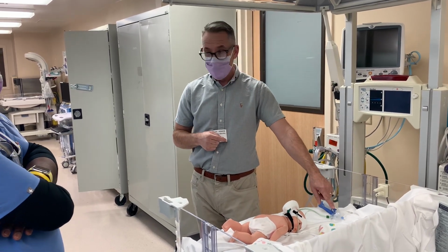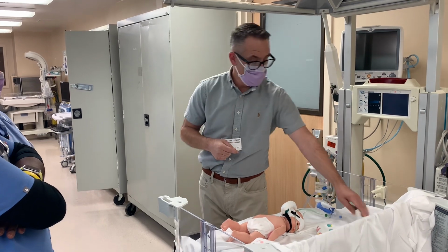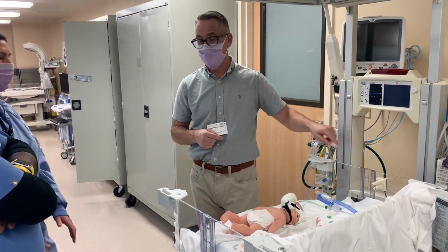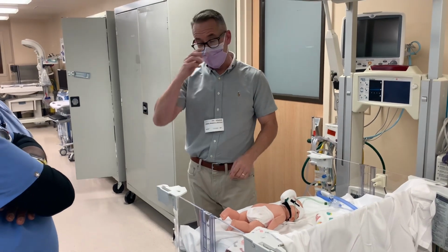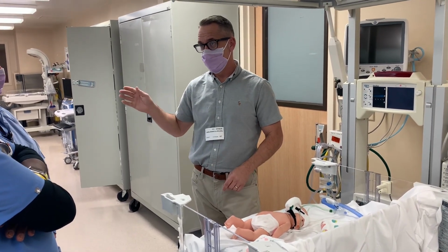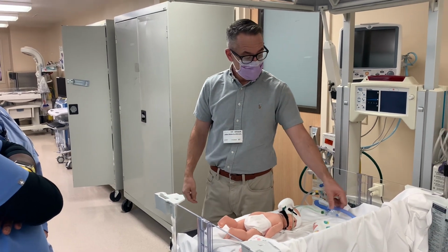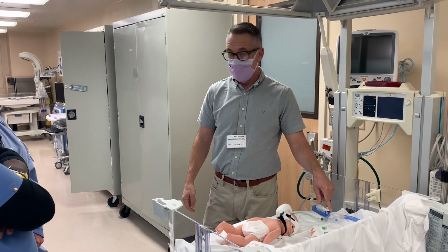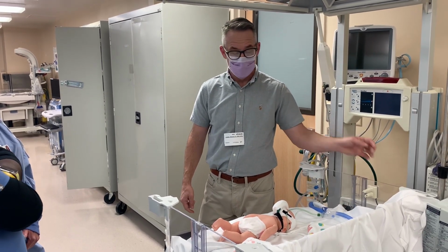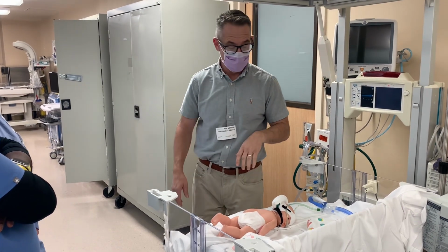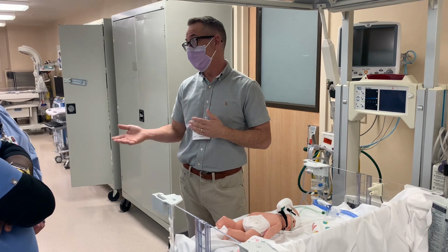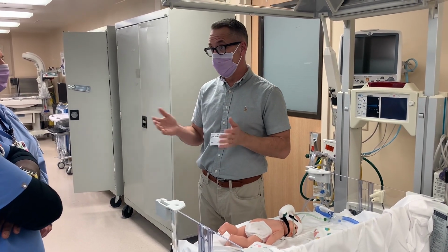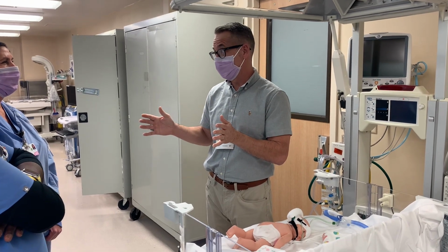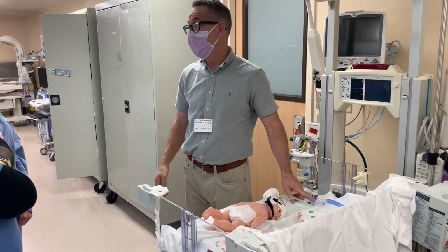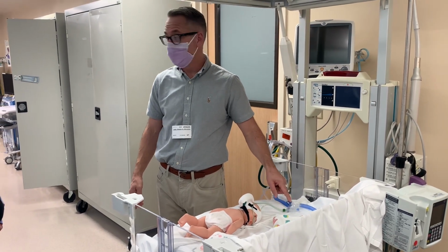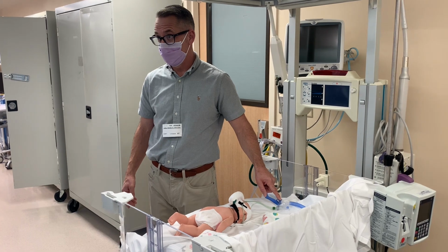People ask, why are you allowing the temperature probe now in the incubator? I've always been told I need the extension unit because we want the temperature probe outside the incubator. The reason why is that back when we used old incubators, we used to set the temperature to 36, 37 degrees manually, and that's what babies would go into, and that used to cause havoc on the temperature probes themselves. And so they created distinct extensions so the temperature probe would stay out. Now with these brand new Giraffes and all the different incubators out there, all the nurses put their babies in the baby mode. If you ever look at an incubator that's in baby mode, it typically stays between 32 and 34 degrees Celsius during the entire time, and that does not cause haywire on these temperature probes. So the temperature probes can go inside the incubator as a result.